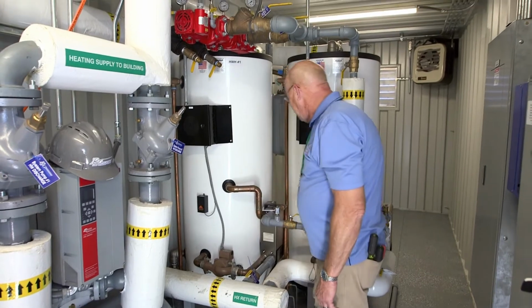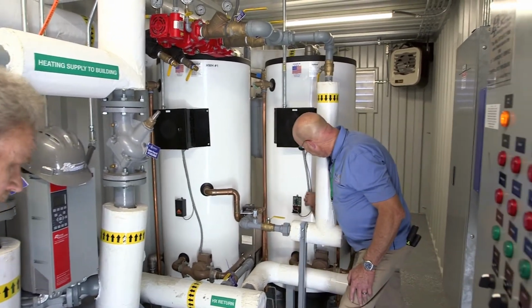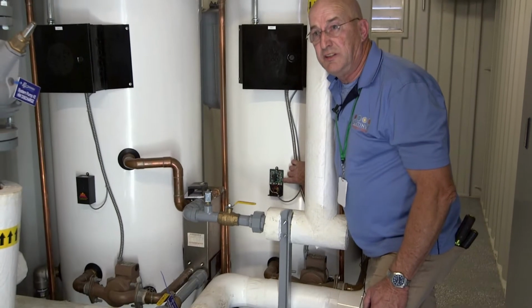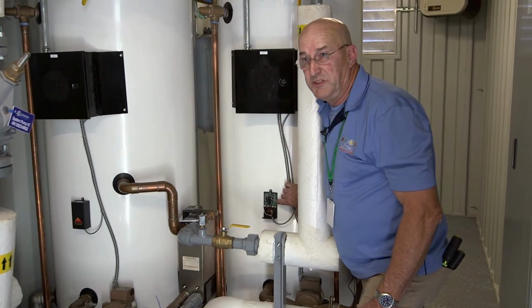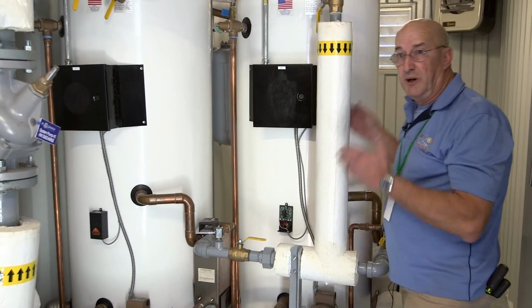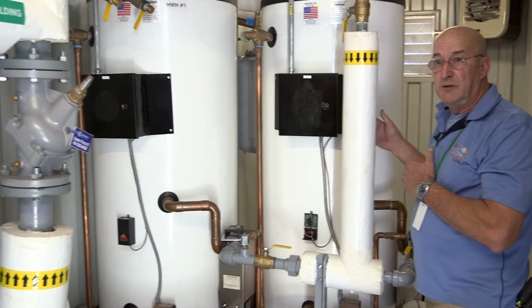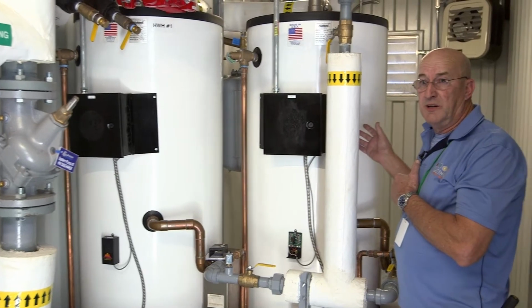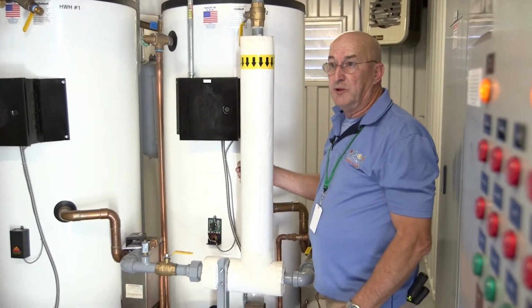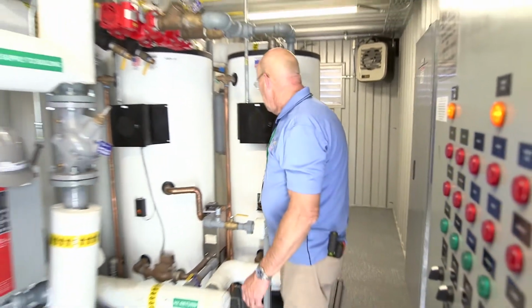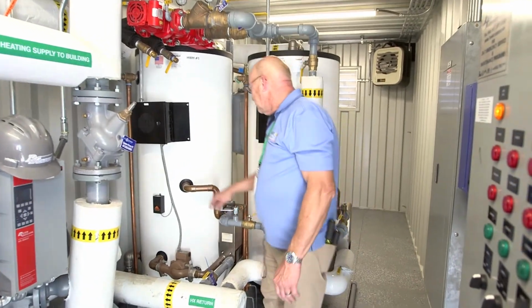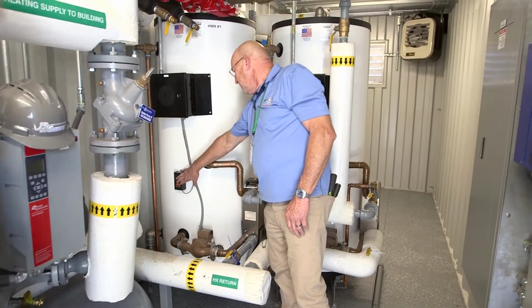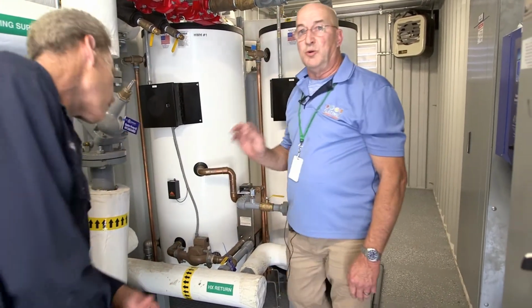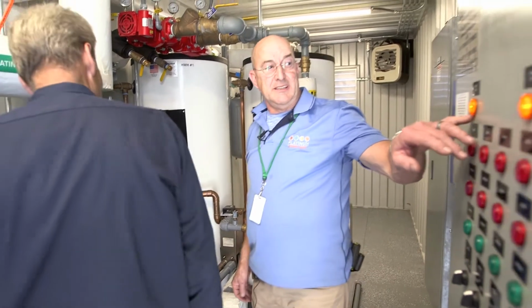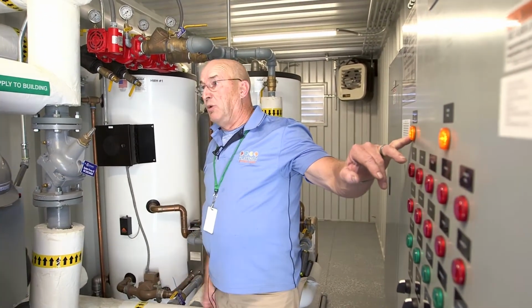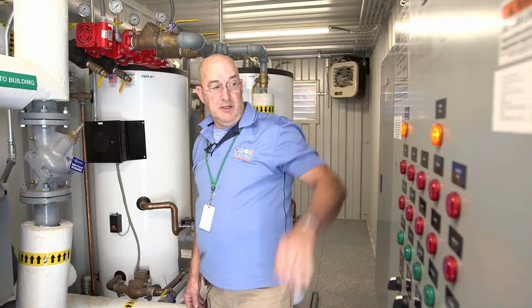This here is the aquastat. You see I took the cover off on this one. This is how the temperature gets set on the tank. The temperature will be set at 135. It has to be higher than what you have at the mixing valve. So the stored water will be going out to the mixing valve at 135, but you'll only have 125 going to the building. You'll see there's a little green light on top here. The green light tells you that it's calling for hot water. There's also a light here that tells you it wants to make hot water.